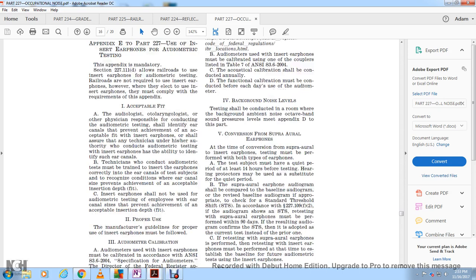Requirement 5: Conversion from supra-aural earphones. At the time of conversion, audiometric testing must be performed with both types of earphones. The subject must have had a quiet period of at least 14 hours prior to testing. Hearing protectors may be used as a substitute for the quiet period. The supra-aural earphone audiogram shall be compared with the baseline audiogram to provide an appropriate check of the standard threshold shift per Section 227.109(f)(2).